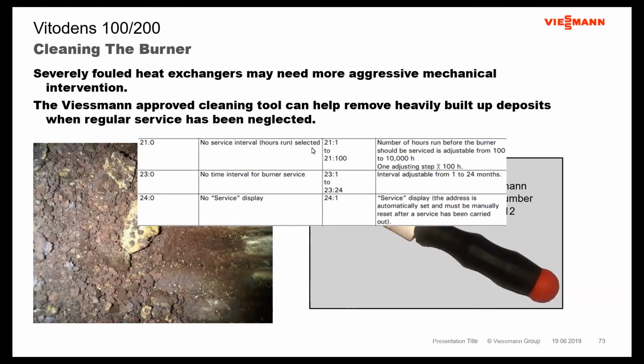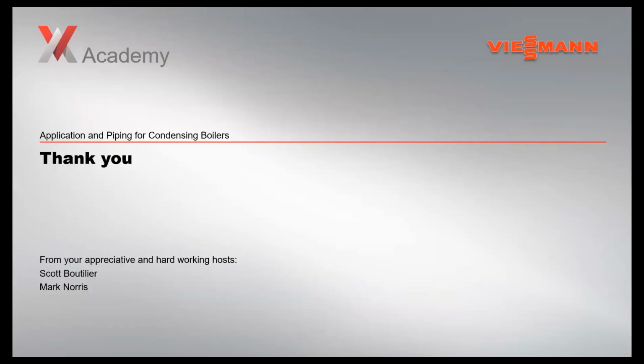Once you go back in and do the service of the boiler, what you'll do as a contractor to reset this timer is go into address 24, where it'll be at a 1. You set it back to 0, push OK, and now it's going to time that 12 months again, or run hours again, until the next service is required. So that's in there as well to give us a reminder that it's time to maintain that efficient heating system for the next year of operation.